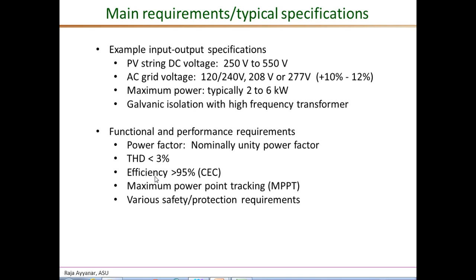The PV inverters are highly efficient, and the efficiency of most string inverters is above 95%. This is a 95% CEC efficiency, which is one form of weighted average efficiency taken at many different operating conditions. CEC stands for California Energy Commission, and this is a standard provided by them for measuring inverter efficiency and to have a standard metric for comparing inverters of different manufacturers.